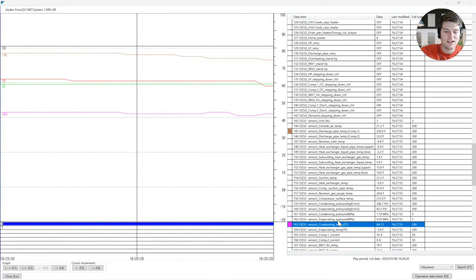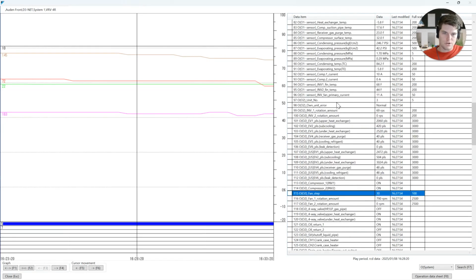Superheat and subcooling, it all varies based upon one number, and that is our saturation temp. This is our saturation in the evaporator. This is our saturation temperature in the condensing area of the system, aka discharge temp, because that's where the pressure sensor is. It all depends on where the pressure sensor is, which we could go on a whole tangent about, which we're not. I'm going to focus. ADHD might be kicking in here a little bit. So discharge compressor temperatures, and we have our condensing temp. Now I have my favorite number, which is discharge superheat.